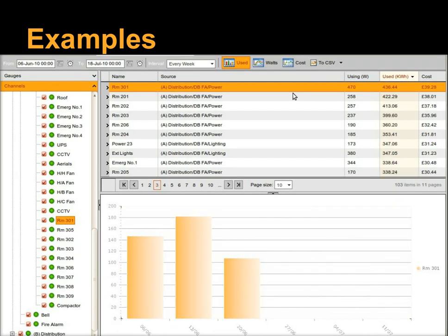But when they ran a cost function over the 6 weeks of the term, here's the AC unit, just that same AC unit, using over £20 a week. This is the week they turned it off. Between when they turned it off and the end of term, they saved over £50. And when they calculated out the whole time, it was like £500 a year. £500 a year times 30-odd rooms with these through-the-window AC units is an enormous amount of money. They were incredibly pleased with themselves.